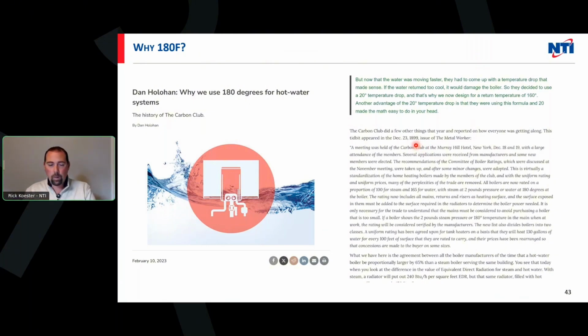But the other part of that meeting was this, think about this: they had steam systems for the most part, 212 degrees of water temp. Then they went to gravity hot water. So we heat that water up. The controls were not great, so they were putting water out almost boiling. And as that water was boiling, obviously with gravity, hot going to cold, it created this flow. They did it on open systems, right? They were open to the atmosphere. So what happened then was pipes started to corrode inside. Once they started corroding, they started to hinder that gravity flow that was going through.